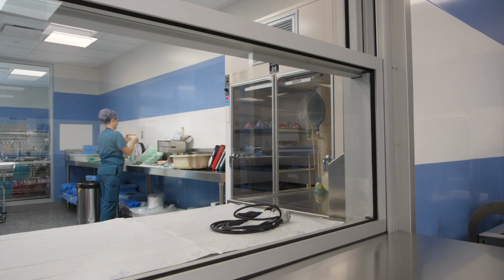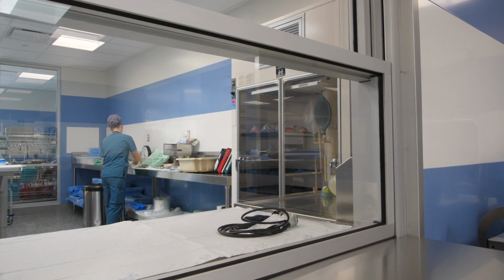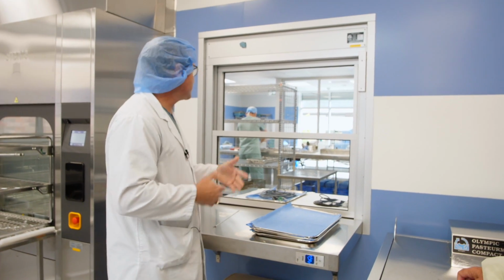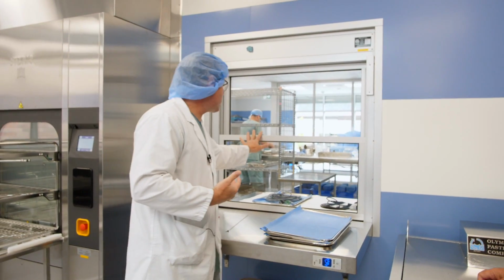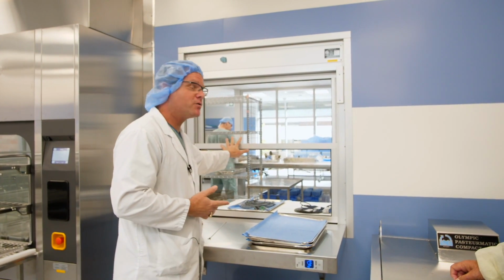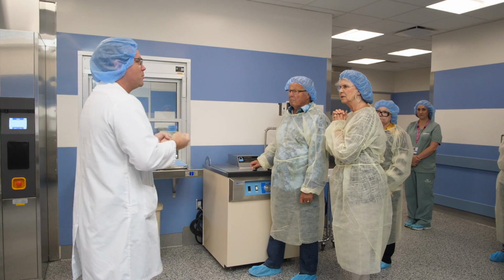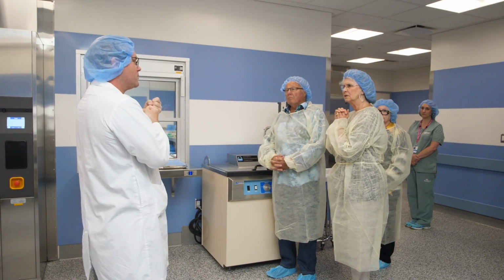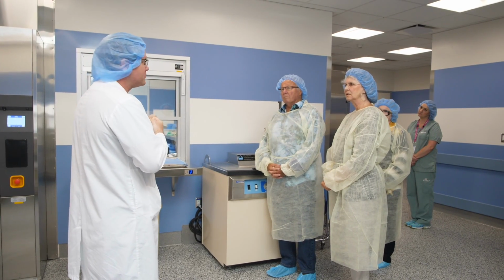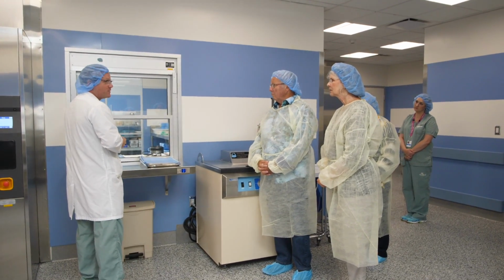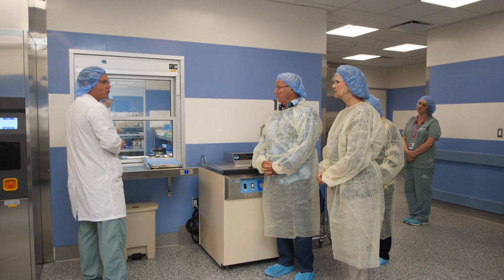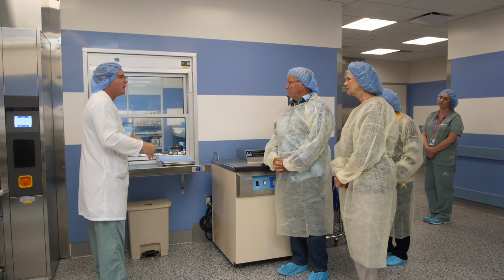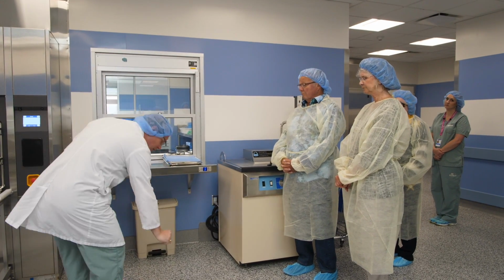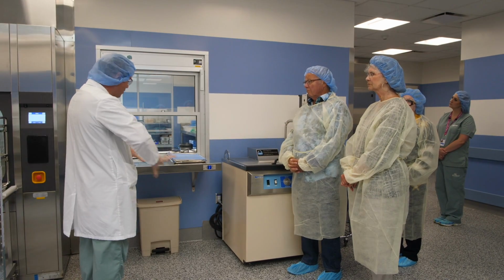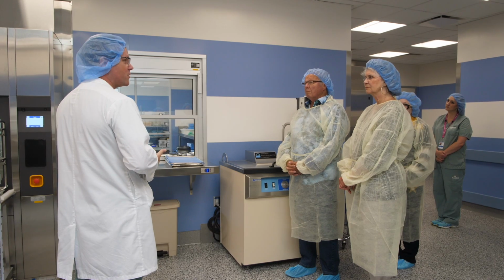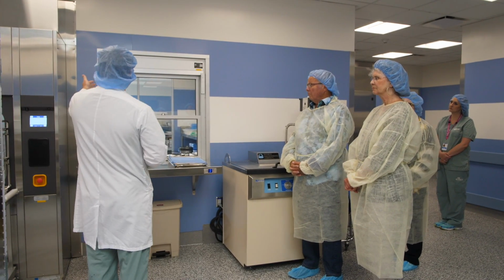We have a pass-through window so that our clean department, if they need to bring stuff back into our decontam areas, either stuff that we believe needs to be reprocessed or stuff that needs to be brought into this area for storage, it gets passed through from our positive pressure side, where it's the most clean, into this side. In this area, we don't want to push it out into our patients. We want to suck it into here. So in our dirty area, we have negative pressure to bring it in. The reverse of that is we don't want that same contaminant to go into our clean area. So our clean area blows air. It creates positive pressure. So anything that goes into that area, from a mite to whatever else you may see walking around, gets blown out of that area and taken into areas like this where they're dirty. So we can complete a distinctly clean and a distinctly dirty area.